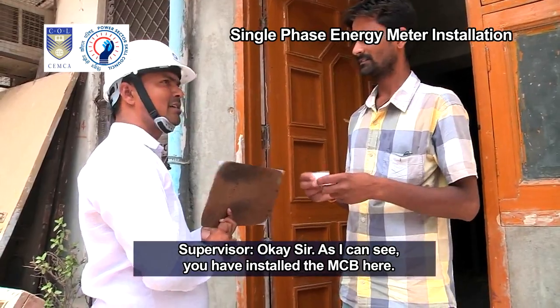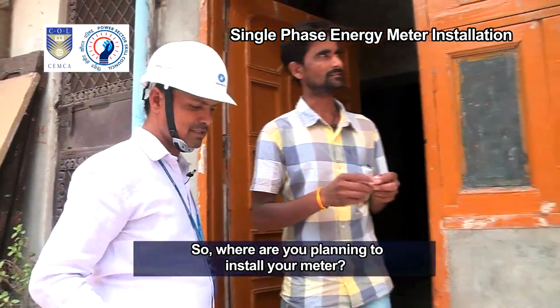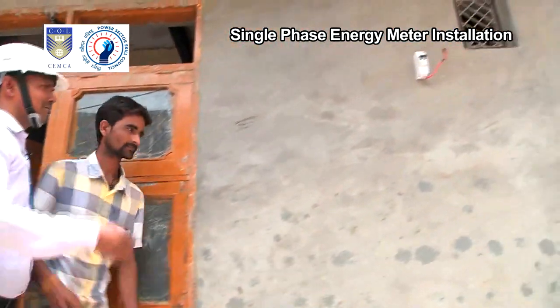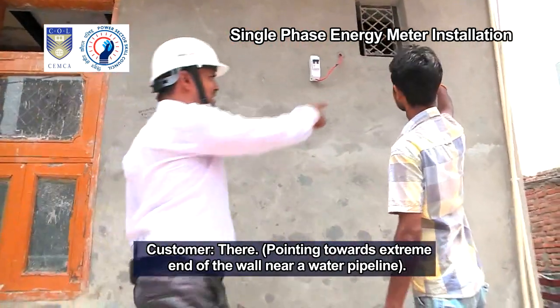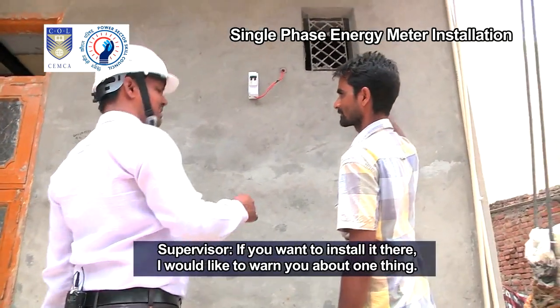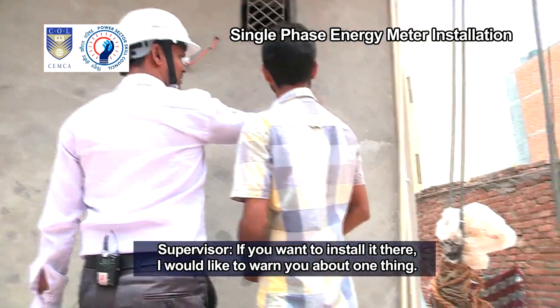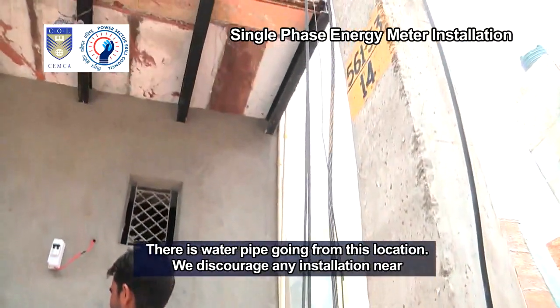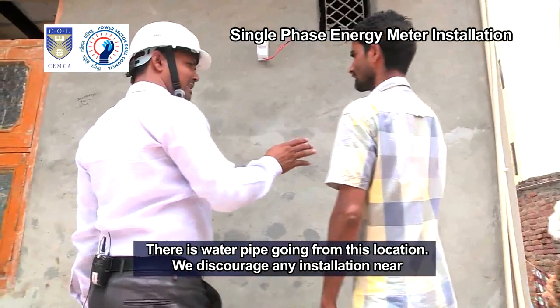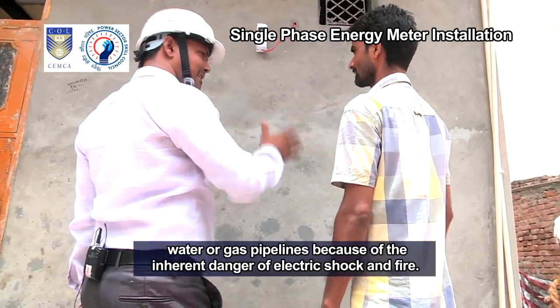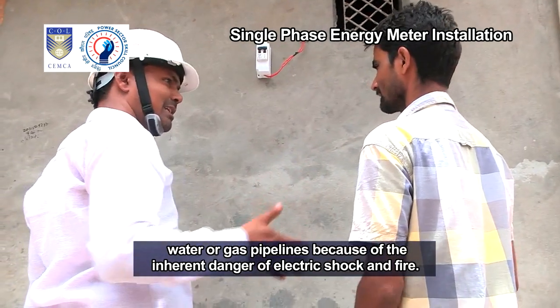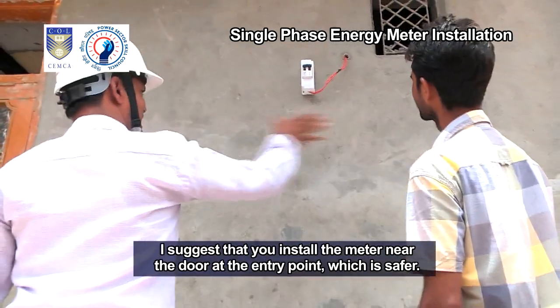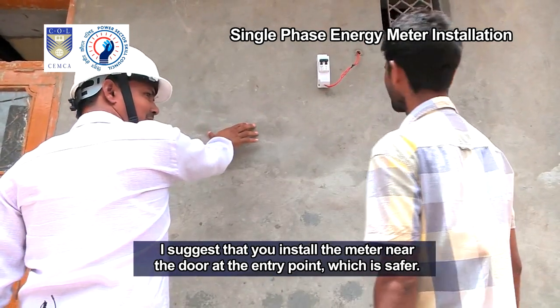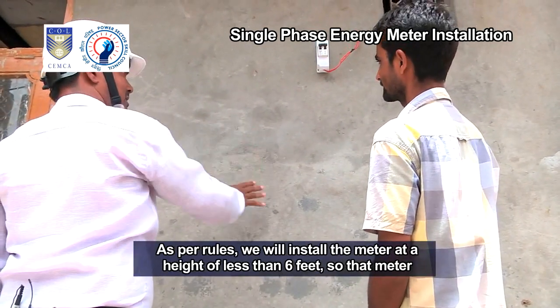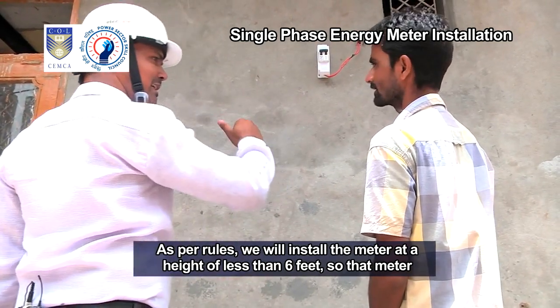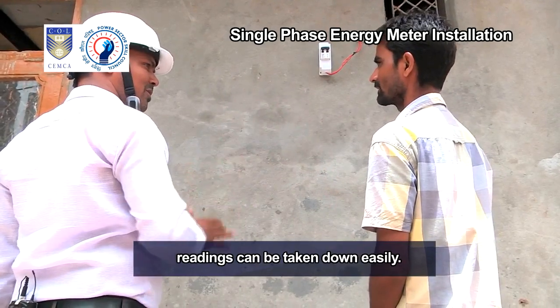As I can see, you have installed the MCB here. So, where are you planning to install your meter? Customer: There, pointing towards extreme end of the wall near a water pipeline. Supervisor: If you want to install it there, I would like to warn you about one thing. There is a water pipe going through this location. We discourage any installation near water or gas pipelines because of the inherent danger of electric shock and fire. I suggest that you install the meter near the door at the entry point, which is safer. As per rules, we will install the meter at a height of less than 6 feet so that meter readings can be taken down easily.